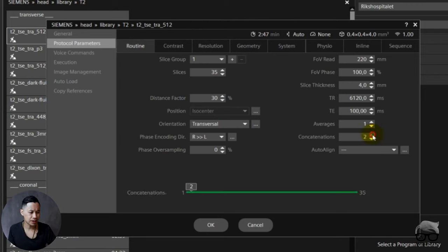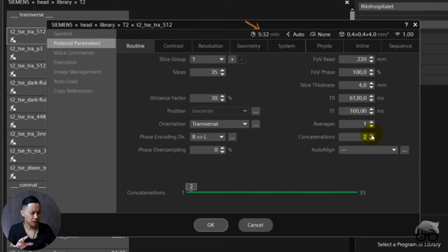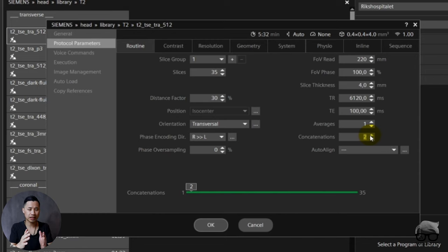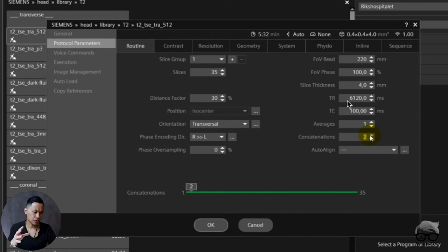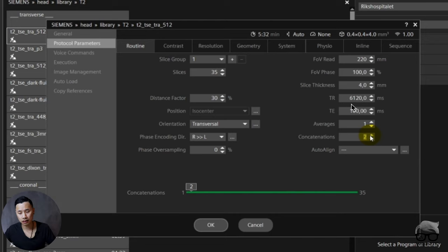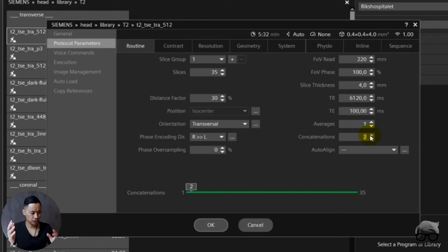What can we do now? Like I said in the figure, this is a long TR of 6000 for being able to have 35 slices. So let's increase the concats. Look at the scan time. We're going from two minutes to now five minutes. We doubled the time, right? For one TR. And now we are doubling it. So we are having an acquisition of 6120, one TR, and then another TR which is the same. Scan time doubles up.